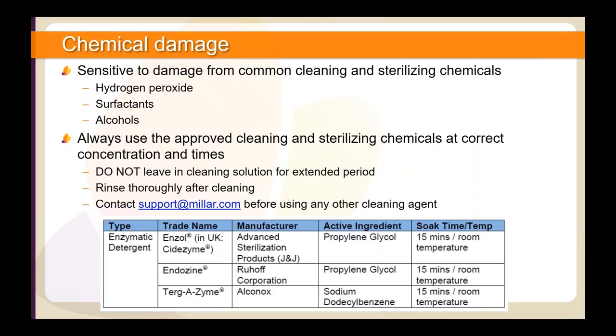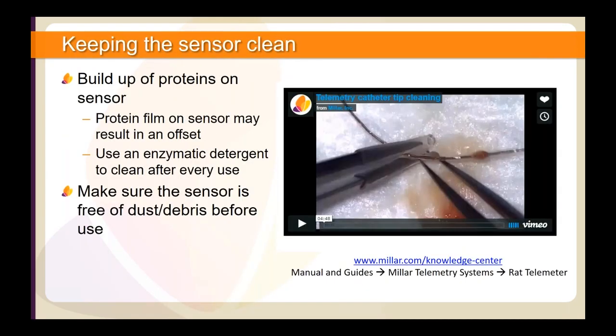It's very important to rinse off any cleaning agent thoroughly after cleaning. This prevents crystallization of the cleaning solution and also prevents interaction with other solutions or with tissue during use. Sterile saline can be used for rinsing prior to implantation, but before storage, distilled or deionized water should be used to prevent crystallization of salts as the saline dries. There is more information about sensor cleaning, including a video, in the Knowledge Centre section of our website. It is located in the rat telemetry section, but it is applicable to any Millar pressure sensors.